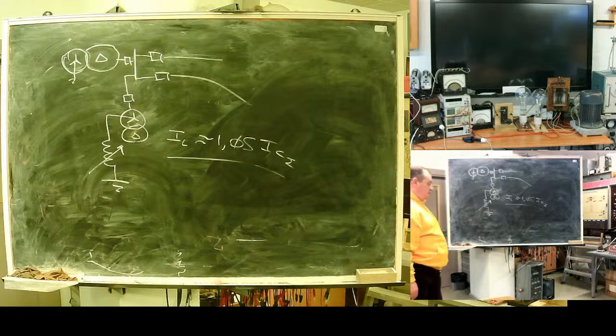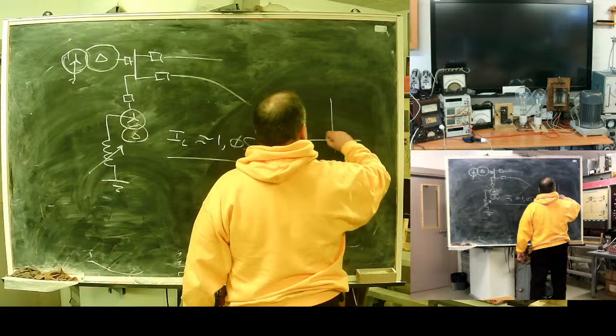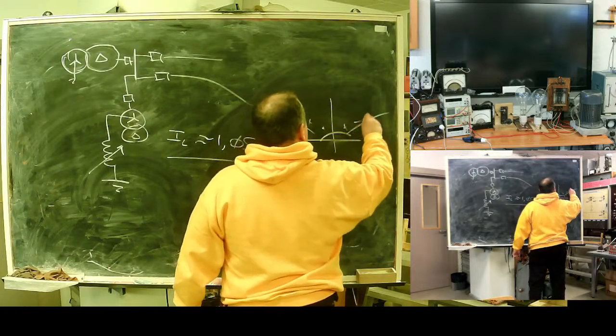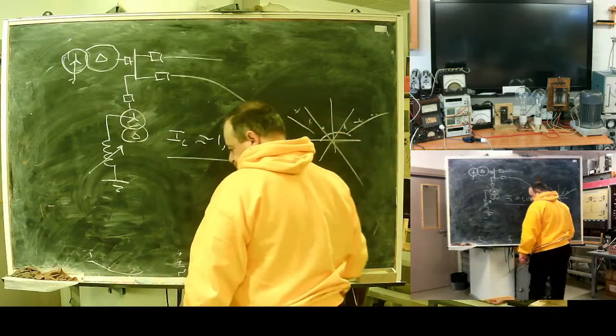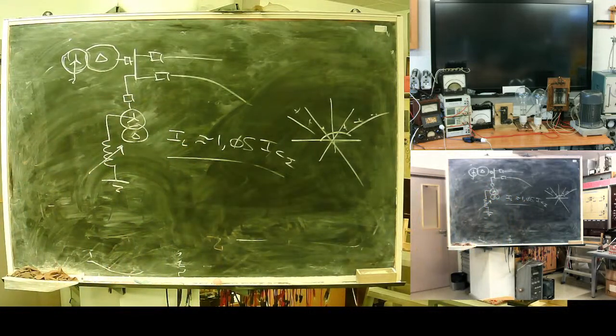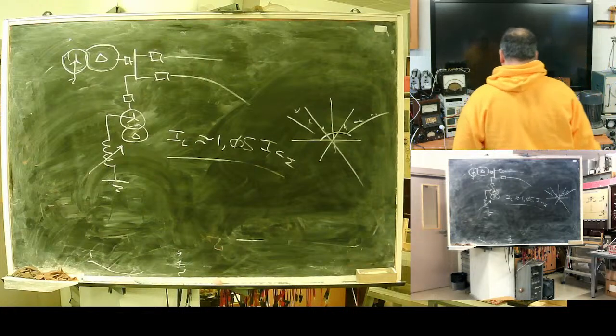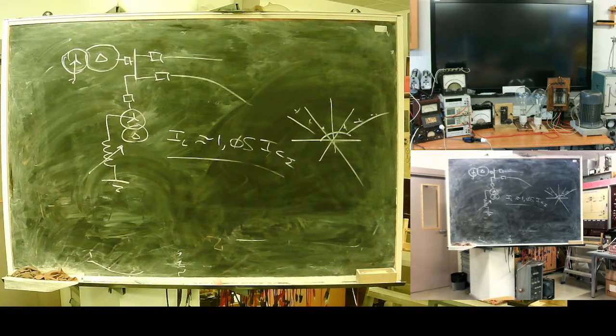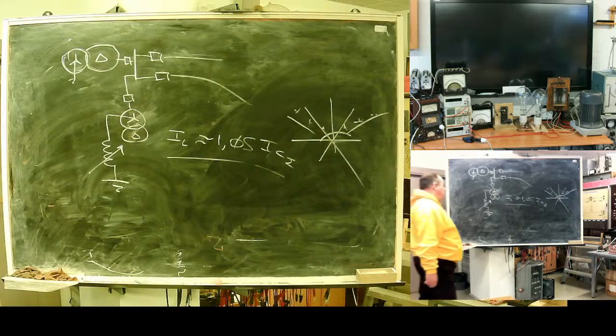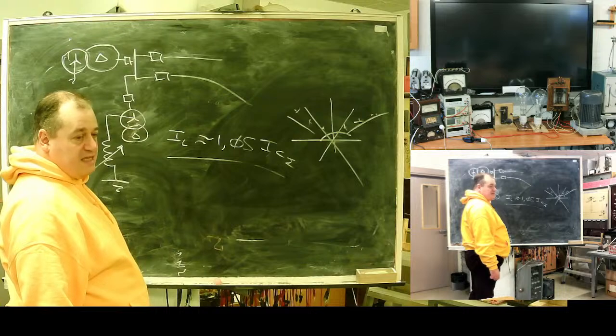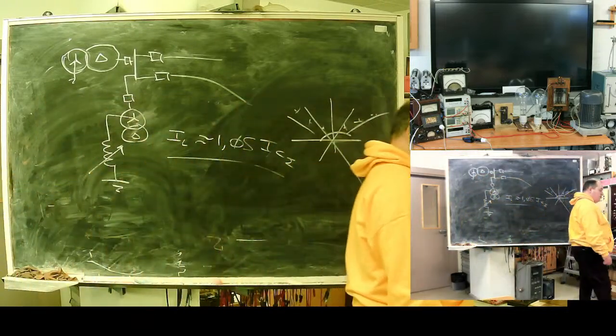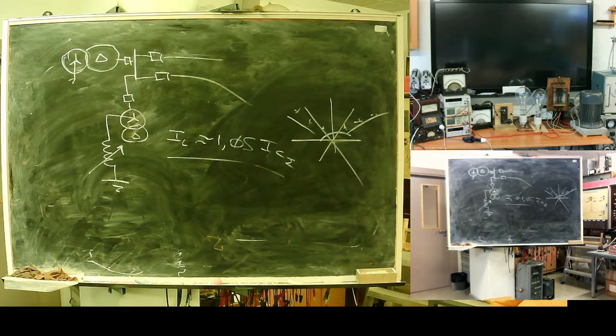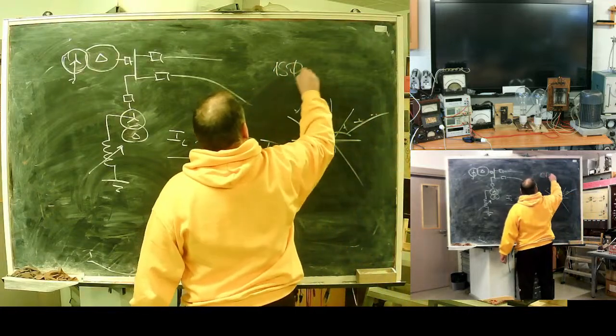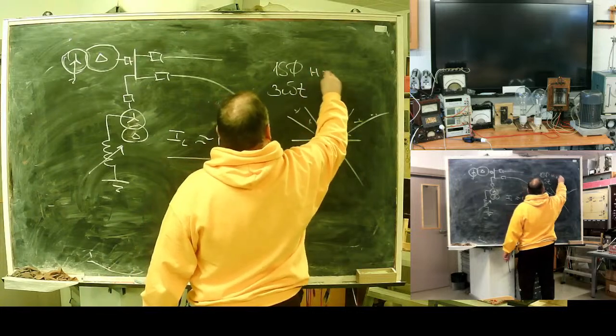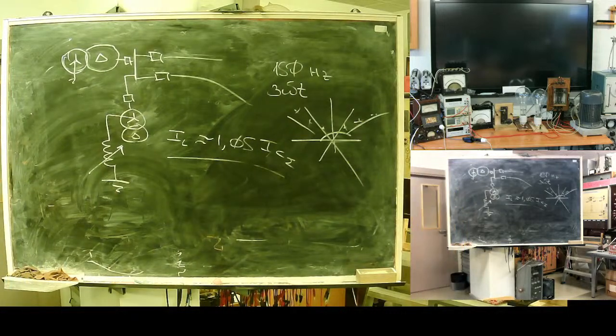So for such a network, a simple characteristic will not work. What can be done? There is no silver bullet. One approach is to use not the 50 Hz component, but 150 Hz, the third harmonic. The network is not compensated or resonant at 150 Hz, since it is compensated only at 50 Hz. Coil resistance is 3 times higher, capacitance resistance 3 times lower. So one idea is to use 3ω, in our case 150 Hz.